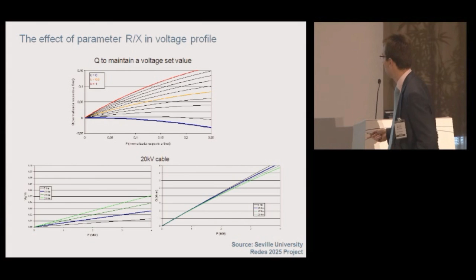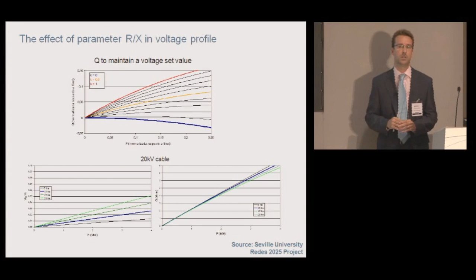So that's quite significant, because that means that in medium voltage and in low voltage, distributed generation, as it is today, is not going to be able to control and maintain the voltage in the grid. What is a quite significant conclusion. Here you have, as a summary, the ratio of the extra reactive power that we need when we are talking about medium voltage. It's very close to 2.5 for cables, and 1.5 for overhead lines.